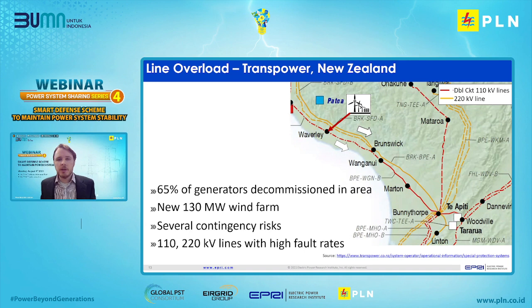So in this case, there's a new wind farm connecting into the Waverley station here at the top. Now, the challenge in this area is that a lot of the generators have been decommissioned. There were a lot of older thermal generator plants, and 65% of these have been decommissioned. A lot of wind has been connected in the area, with this one 130 megawatt wind farm in particular. So with these parallel lines, there's a risk of contingency overloading. And in this area, there are very high fault rates. There are many lightning storms and wind storms, which cause the lines to trip.